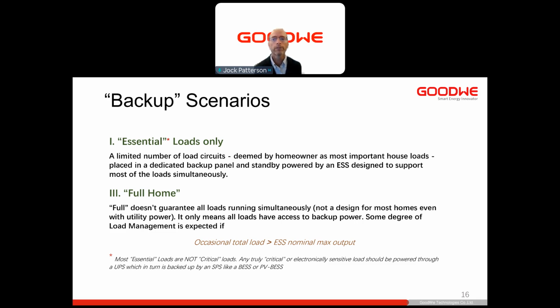And if you're doing essential loads, it's important to choose the right ESS for it. For full home backup, this doesn't mean running all loads in the home simultaneously. Like we have to explain to the customer, the full house backup means that all loads have the potential to receive backup power, but some load management might be required because you do not want the case where your total load exceeds the output of the ESS system, or that system will shut down.